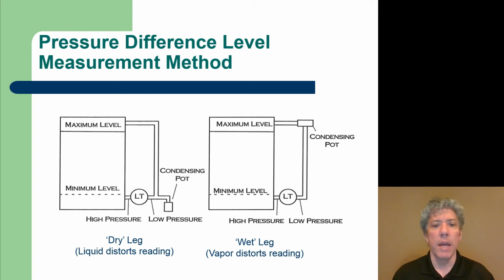and that difference in pressure can then be used to infer the height of the liquid column. Now if liquid does condense, if it evaporates and condenses in the leg, then it will run down and needs to not be in that right leg. The right leg needs to be dry, and so what has to happen there is the liquid goes over and down to the condensing pot. There's another, and that way it can be removed and either put back into the tank or discarded. There's another type called the wet leg, where vapor distorts the reading, but we won't go into that one for now.